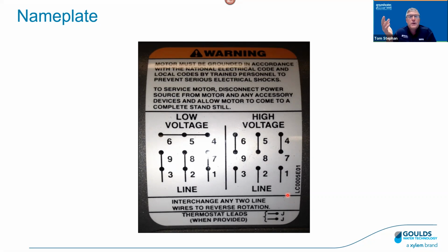Let's just say in our case we are going to bring 230 volt into this motor. Therefore we want to wire it up for 230, or for low in this case. So we're going to look at the diagram for low, and if you've never done this before, it can be a little confusing. We can see that numbers 4, 5, and 6 are tied together.